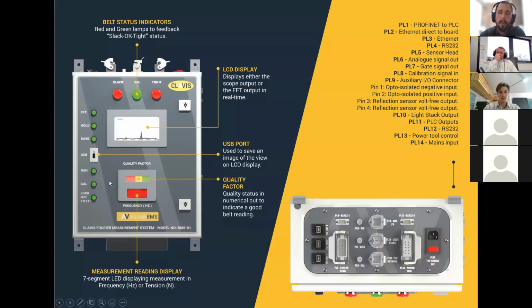So we can look at both the raw data, aka the vibrations coming from the belt, or we can look at the FFT, which we are going to talk about a bit later. And also we have a quality factor, which is an easy way for the operators or the process people to determine whether the quality of the vibrations is correct. And then we have the display for the frequency. On the top of the cabinet, we can see that we have a lot of IOs and the ability to have a light stack as well. We have RS-232 communication, and then we can have Ethernet communication as well.